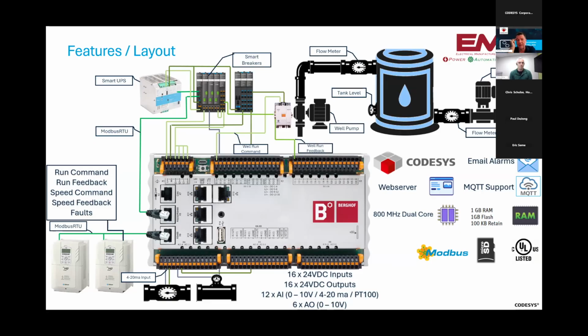The other thing that's nice about this is if you have a short or an overload, we get notified immediately. So that in and of itself allows the operator to know, hey, it was a digital input that shorted, a digital output that shorted or overloaded, analog in or analog out. And basically each one of those is on its own breaker. That allows us also to be able to reset that remotely. In the event of that failure, I can now go back and say, let me try to do a reset. Maybe it was a nuisance trip. I think everybody on this call knows there's no such thing as a nuisance trip. Something has happened, but it might save them a drive out to that remote site so that they do not have to worry, at least that night, to go out and correct something. Kevin, anything to add here?